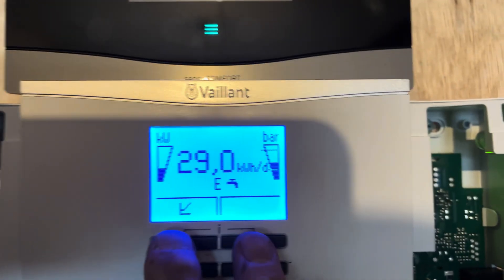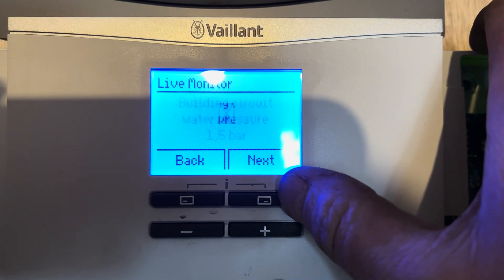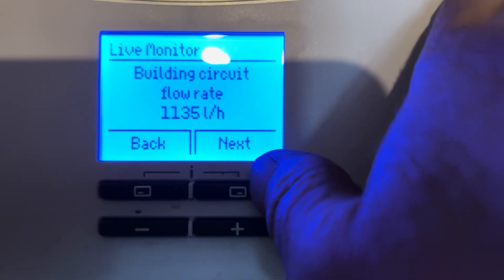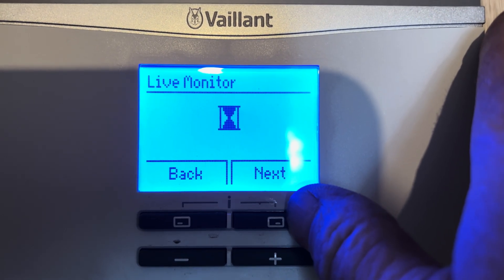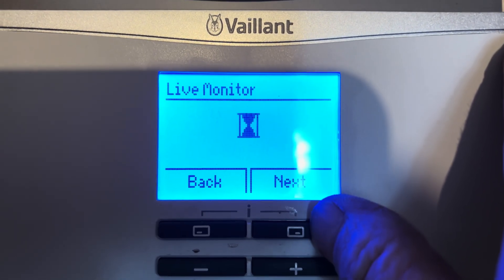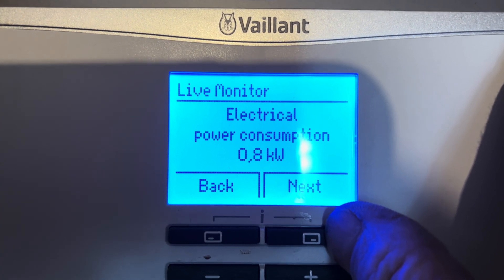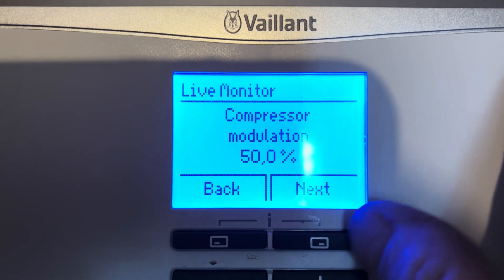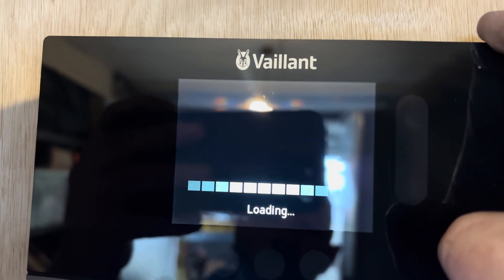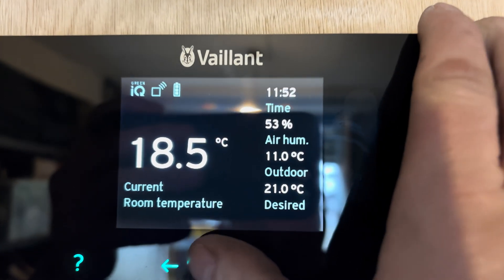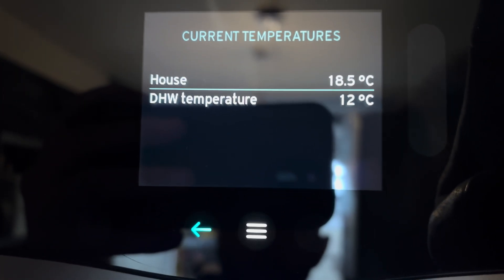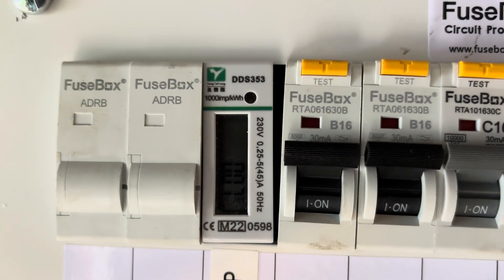So we're five minutes in now, you can see we're doing hot water still. Let's go through the live monitor to see what's going on. Press is active, water pressure is good, flow rates are good. Target flow temperature 58, current flow temperature 20. We're using 800 watts at the moment. Compressor modulation's at 50%. Outdoor temperature is 11 degrees C. We've gone up one degree C in five minutes. We can see we've used 0.07 kilowatts of electric so far.